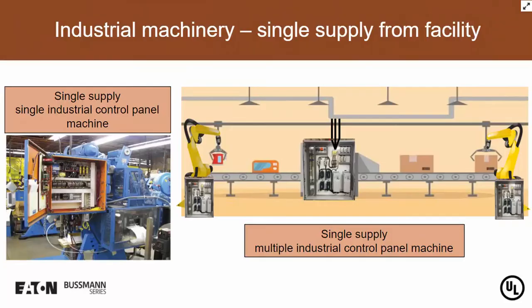So let's move on and talk about determining the overall machine short circuit current rating. Joe's given us a lot of good background, and so let's put it to use. Let's first talk about the easiest scenario in terms of determining the short circuit current rating. That's where you'd have a single supply to the machine, and the machine having a single industrial control panel. In that situation, it's very straightforward. Whatever the short circuit current rating is for that particular panel, then that would become the short circuit current rating for the machine. Very straightforward.